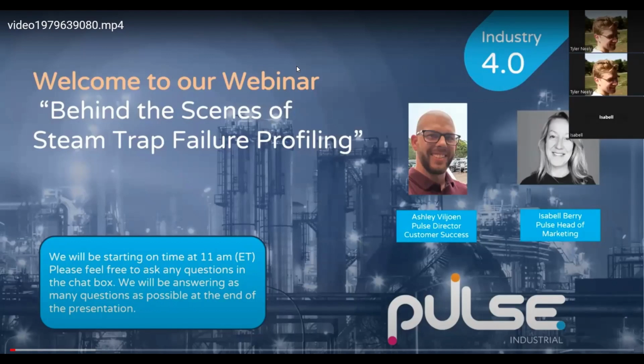Because if a trap is failed and we're installing our sensor onto the trap, there will never be a fluctuation in any sort of data. The temperature or the sound, for that matter, would stay the same. So that's why having that original baseline of how a trap behaves at the start will tell us if there is a failure. You'll be able to see the change.